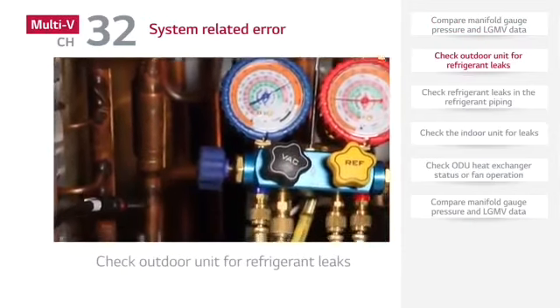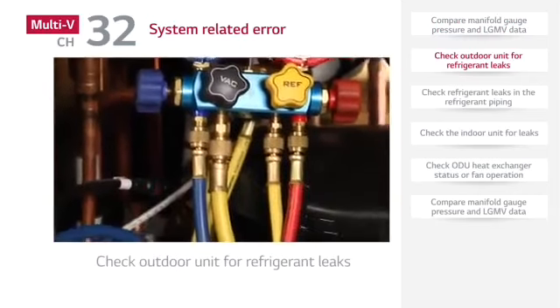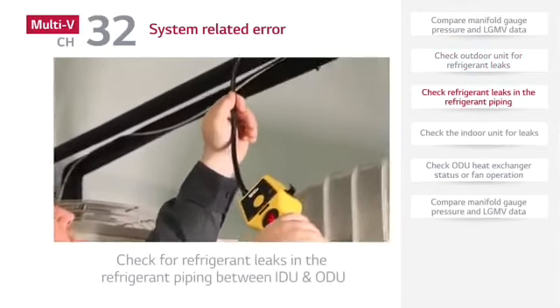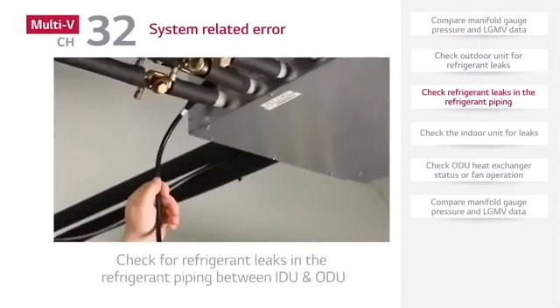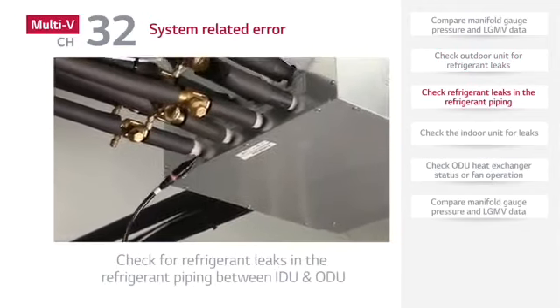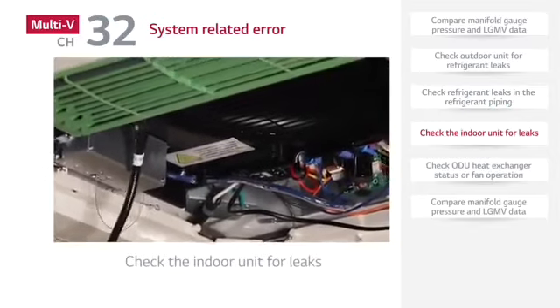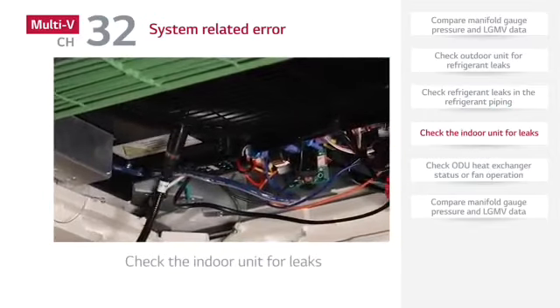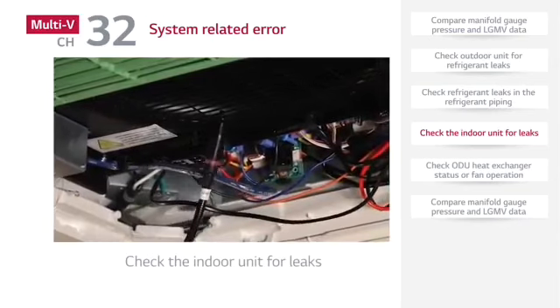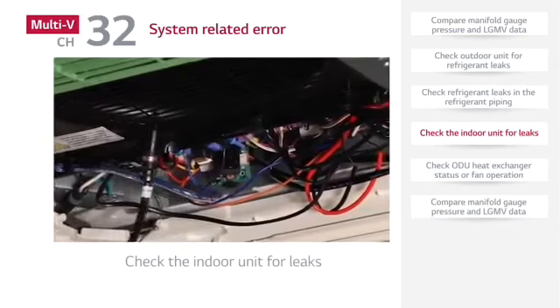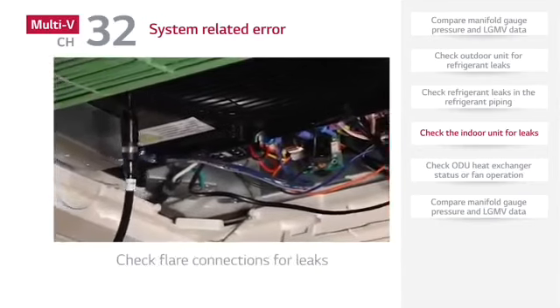If the refrigerant level is low during heating operation, a CH151 error may occur. Next, check for refrigerant leaks in the refrigerant piping between the indoor unit and outdoor unit. If there are no leaks in the refrigerant piping, check the indoor unit for leaks. Be sure to check the field flare connections for leaks.